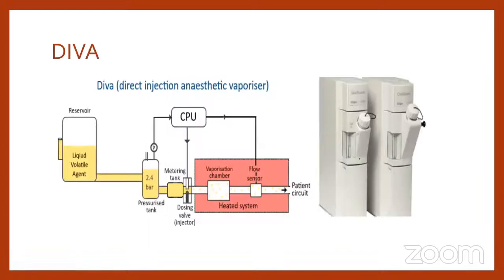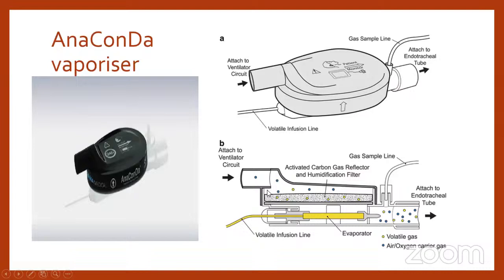The next one is Diva. This is another type of system, basically a direct injection anesthetic vaporizer. The reservoir has some volatile agent, which is drawn into another smaller compartment. Whenever we give an input to the system, the CPU automatically injects the amount of liquid necessary and it is vaporized in this chamber. It goes to the flow sensor. The fresh flow enters the system and is sent to the patient. This is the latest, recent Anaconda vaporizer. This is present at the patient end, not at the machine end.